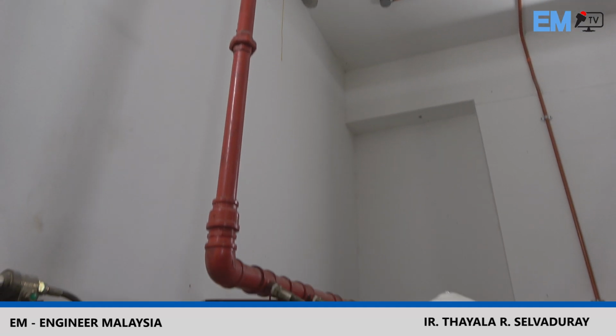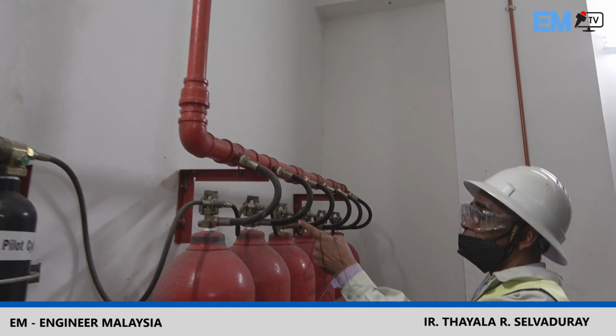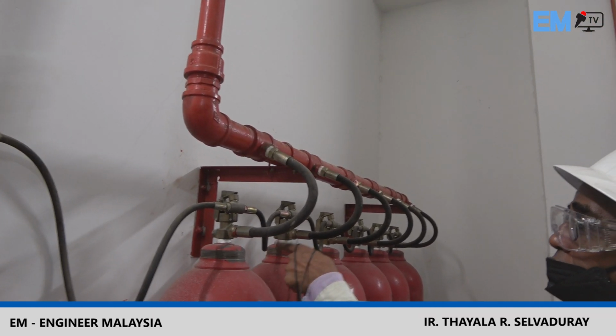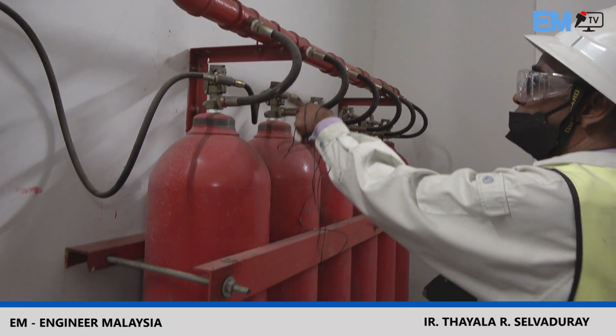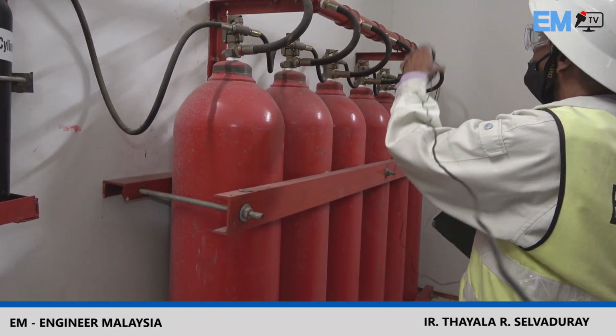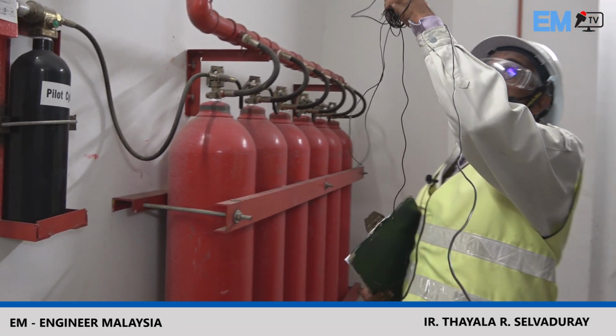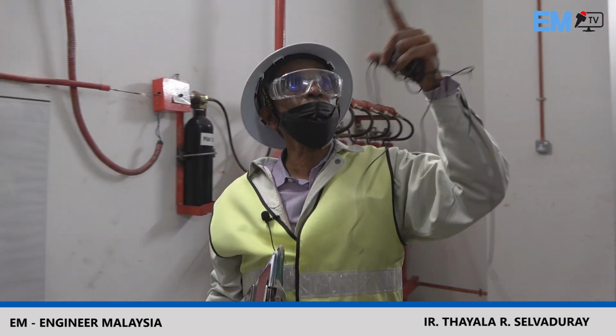It's very cloudy, and one by one the same pneumatic cylinder will go and activate the next and the next and the next. All of them will energize, and the gas is out there, and within 30 seconds plus you will have this whole room filled up with white smoke. No one can see each other, and there's no oxygen in the room. So if you are in this room, it's considered you're very unlucky in an unlikely situation.